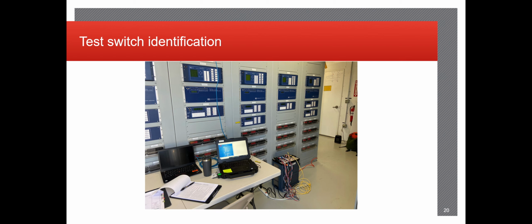This is an example of an existing control house with all the relay equipment, all the test switches, and it seems like someone's doing some relay testing as well. So as I said before, it's really common for the clients to want the relays themselves installed above the test switches for sake of ease and safety precautions. We can see the table might be covering it up, but they're probably utilizing one of those paddles that I showed you earlier, and that's where you'll connect your wires from your test set, which is shown below to the right of the desk. Those plug in very easily. They're way better than having to screw in lug nuts to the back of the relays and plugging them in that way. It's simply just take the paddle, plug it into the test switches, and start testing.